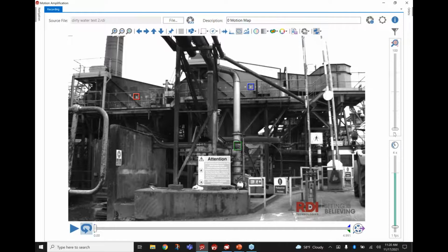Yeah, good question. So the distance doesn't affect the accuracy of the frequencies at all. What the distance will affect is the lowest amount of vibration that you can see. We sort of spec that at 1 meter away with a specific 50 millimeter lens, you can see down to 0.01 mils or 0.25 microns. If you move to 2 meters away, you can see down to 0.02 mils or 0.5 microns. And so you can imagine that's how the distance will affect it, by the amount of smallest displacement you can see. But it doesn't have an effect on the frequency. So the frequency accuracy will stay the same throughout different distances.